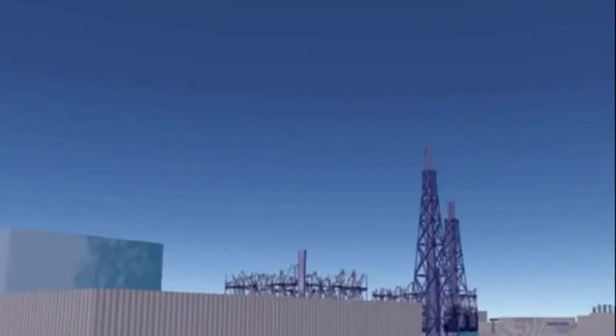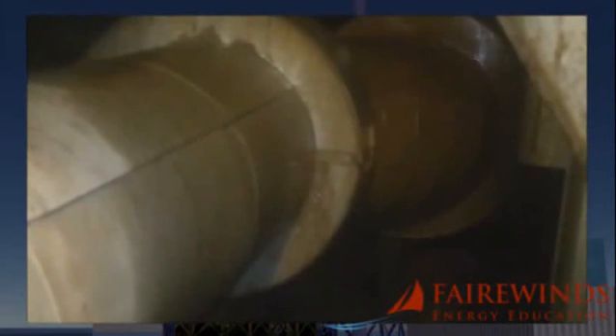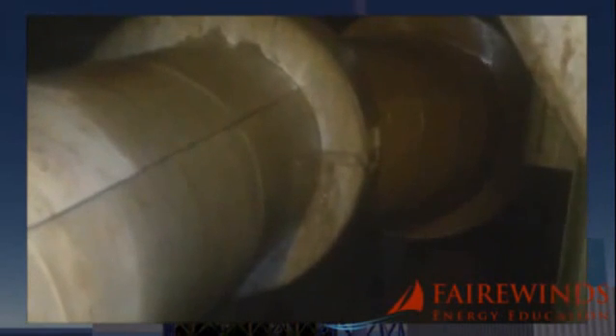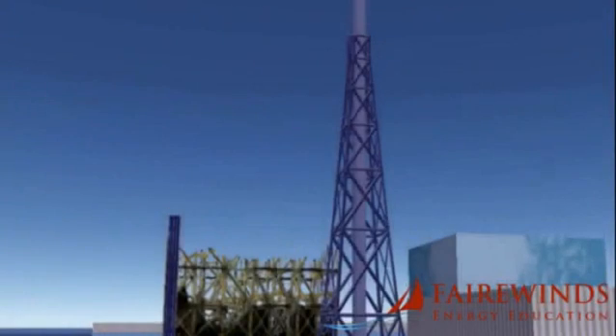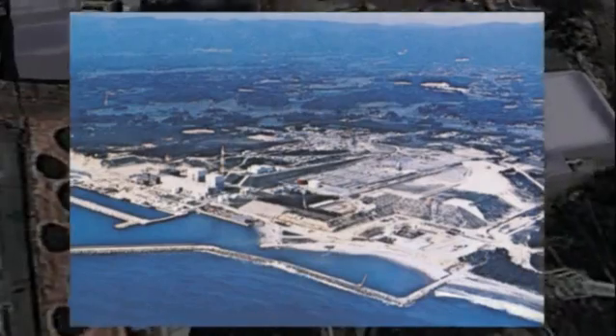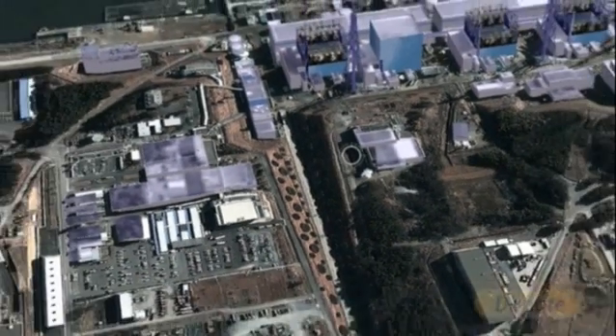So the decision to put Fukushima Daiichi near the water was made by General Electric and Ebasco. Now, of course, that had effect on the tsunami, and we won't talk about that today. But now it's a leading cause of the problem with the groundwater. The high area has a lot of groundwater in it. And where is it going? Water flows downhill right into the basement of these power plants. So the decision to cut away the bank that was made in 1965 by General Electric and Ebasco is the fundamental problem on this site, because it's causing the basements to flood.